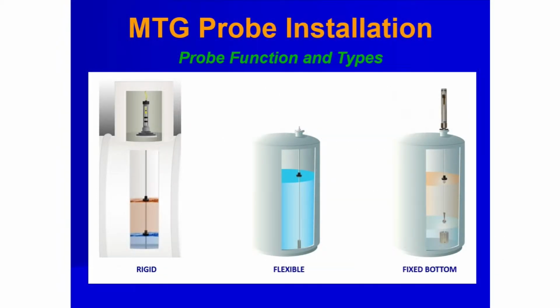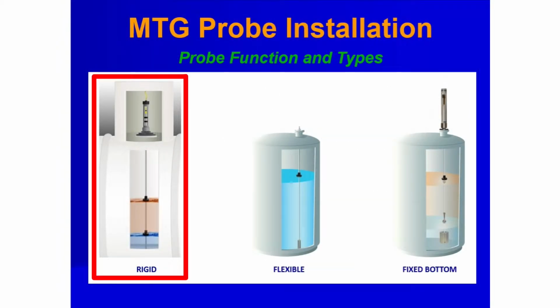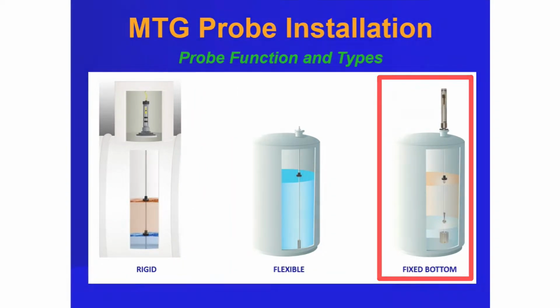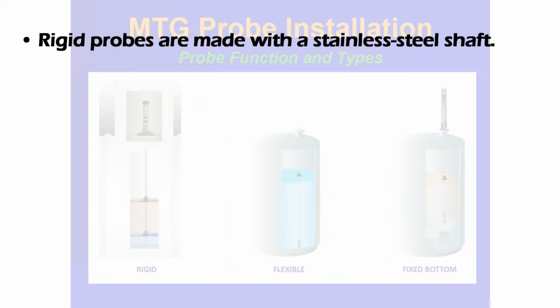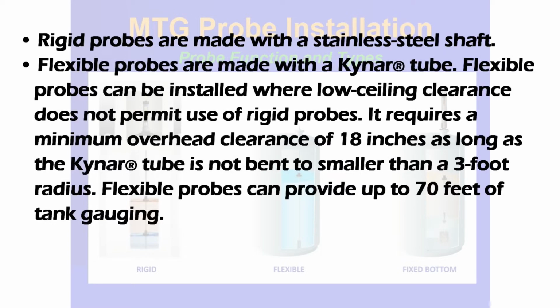There are 3 types of MTG probes: rigid, flexible, and fixed bottom. Rigid probes are made with a stainless steel shaft. Flexible probes are made with a Kynar tube. Flexible probes can be installed where low ceiling clearance does not permit the use of rigid probes. It requires a minimum overhead clearance of 18 inches, as long as the Kynar tube is not bent to smaller than a 3-foot radius. Flexible probes can provide up to 70 feet of tank gauging.